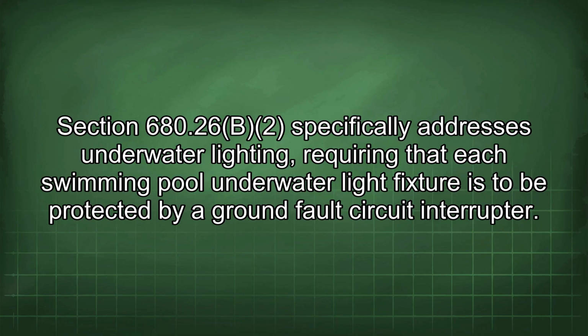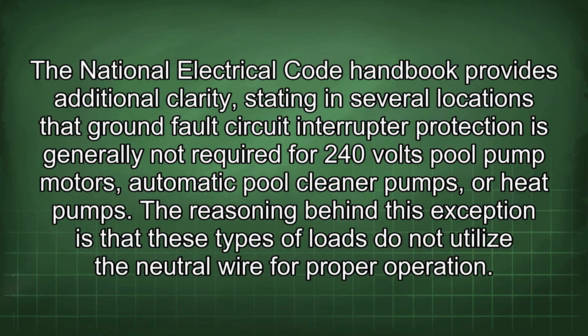Section 680.26(B)(2) specifically addresses underwater lighting, requiring that each swimming pool underwater light fixture is to be protected by a ground fault circuit interrupter. The National Electrical Code Handbook provides additional clarity, stating in several locations that ground fault circuit interrupter protection is generally not required for 240-volt pool pump motors, automatic pool cleaner pumps, or heat pumps. The reasoning behind this exception is that these types of loads do not utilize the neutral wire for proper operation.